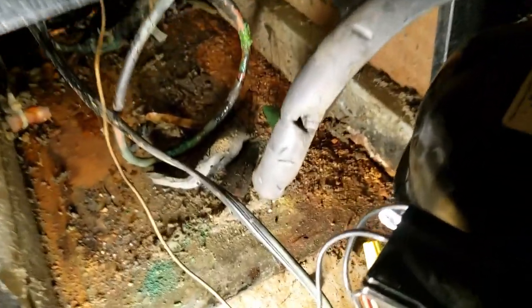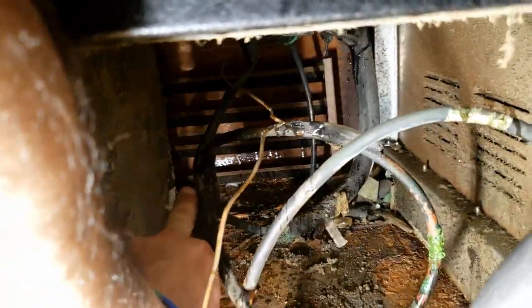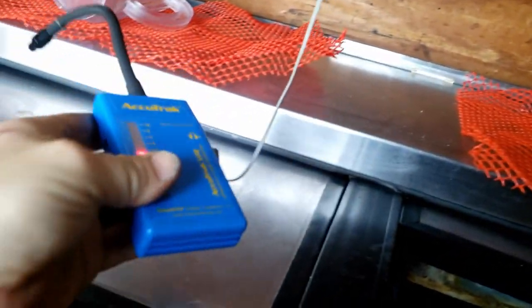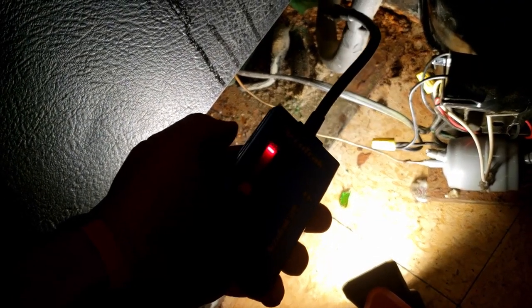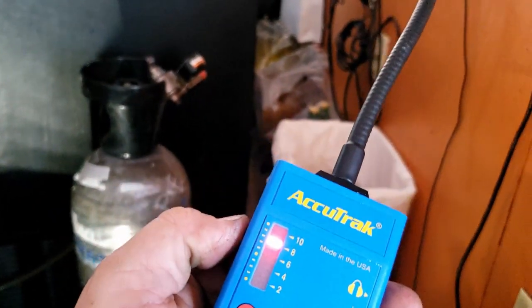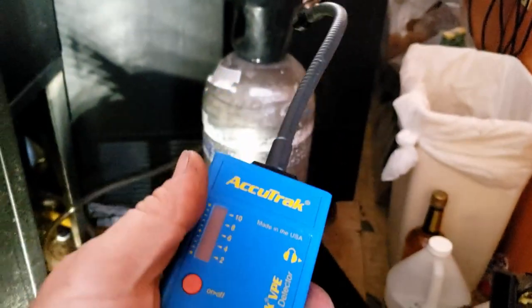I can hear the leak plain as day — it's right there on that fat section where they went from a small tube to a big tube and sleeved it. Something punctured it right below that joint. The AccuTrak ultrasonic leak detector picked it up in a heartbeat. They've got animal rodent repellers in here which are making the detector go nuts, but you can clearly see that's where the leak is. That's where it is — we're going to see if we can fix it.